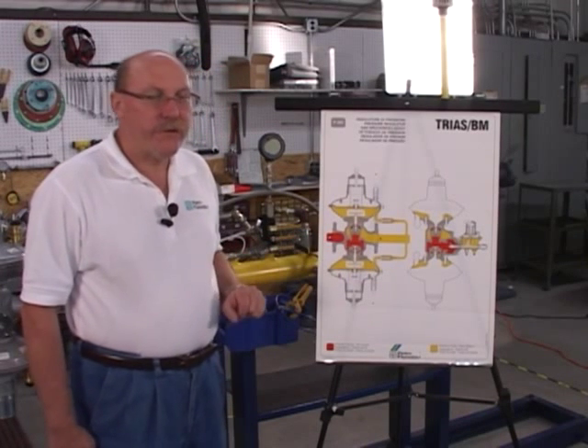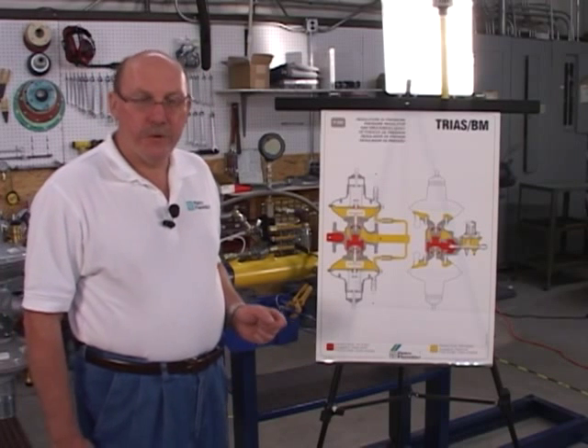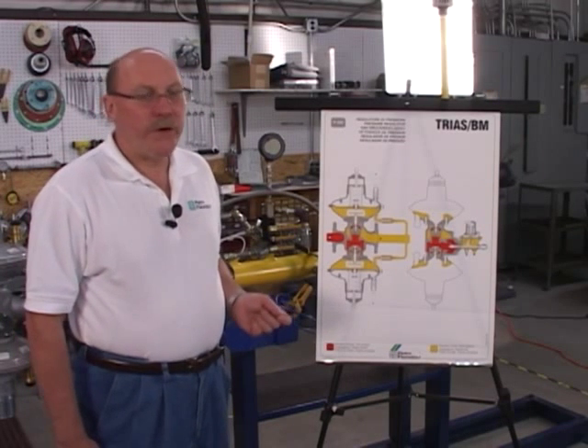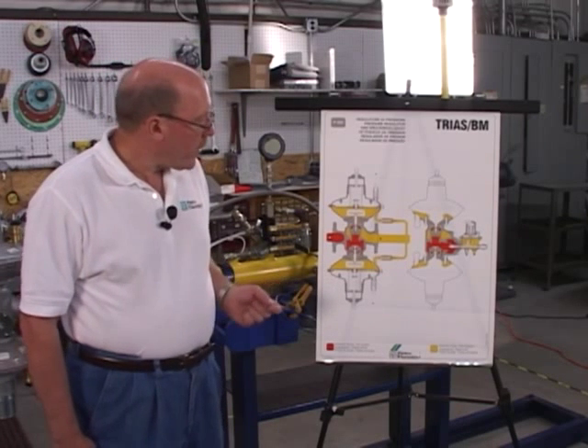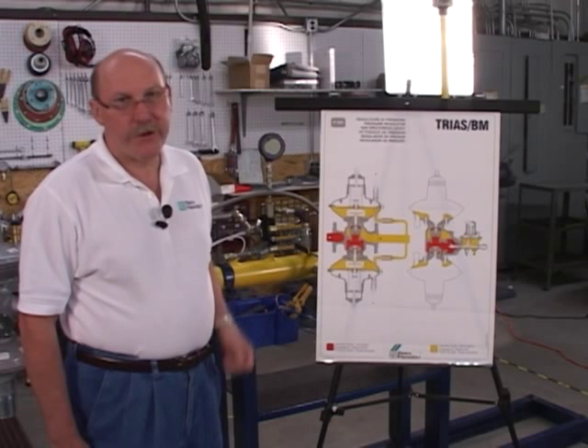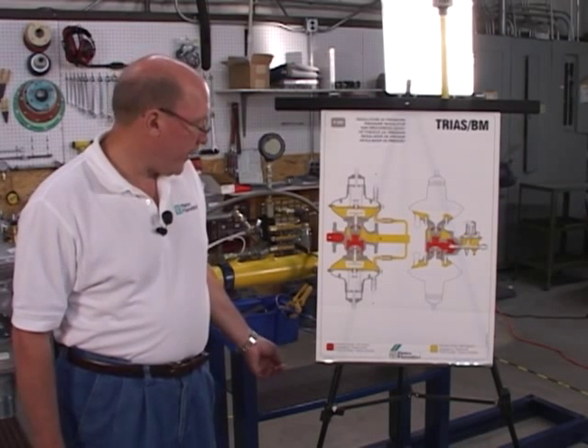as well as the area of the orifice. So what we're actually doing is using the inlet pressure to operate the regulator and using the spring only to control your outlet pressure. Number one, it gives you very, very tight outlet pressure accuracy. The second thing it does is give you very, very high turndown — 500 to 1 on the TRIAS.